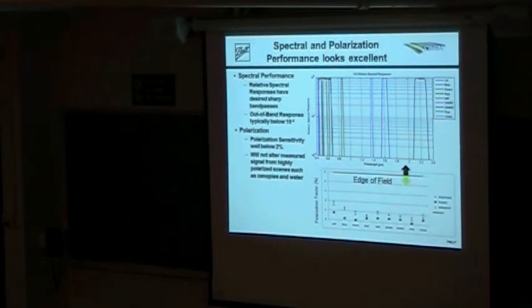We had to show that those met a very narrow spectral performance range for center wavelength as well as band edges, and also the out-of-band response of these had to be better than about 4 orders of magnitude down from the in-band response, which was also challenging to measure. The polarization factor, if you look at the ratio of your highest polarization to your lowest divided by the sum of the two, that's defined as the polarization factor. Our requirement was 5%. We were measuring across these various bands somewhere in the 1 to 2% or better range. So very good instrument. Next.